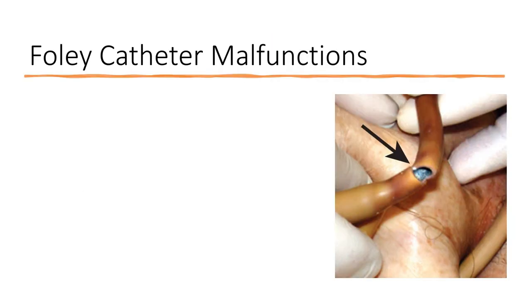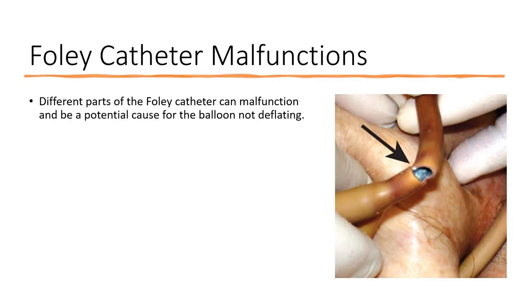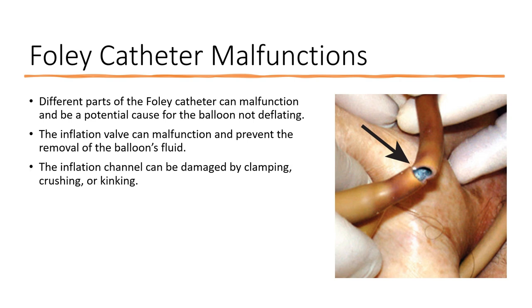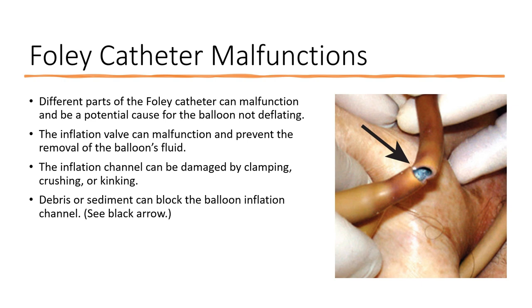Foley catheter malfunctions. Different parts of the Foley catheter can malfunction and be a potential cause for the balloon not deflating. The inflation valve can malfunction and prevent the removal of the balloon's fluid. The inflation channel can be damaged by clamping, crushing, or kinking. Debris or sediment can block the balloon inflation channel.